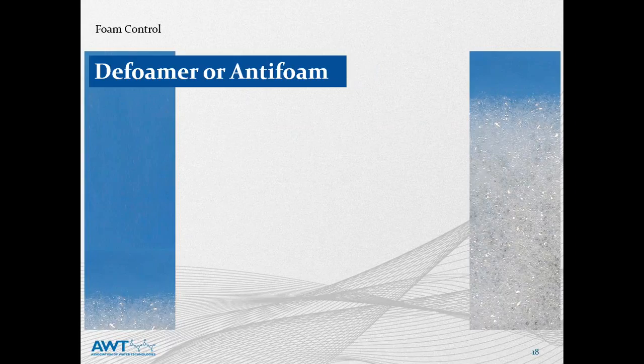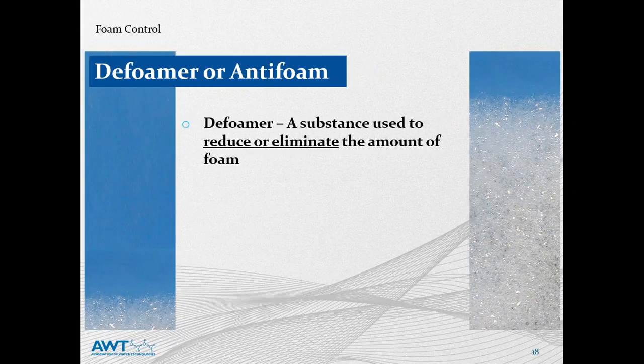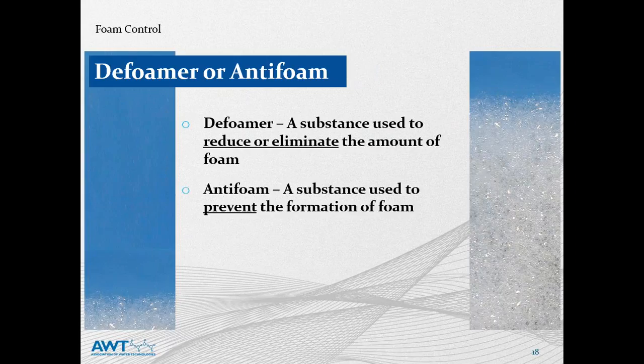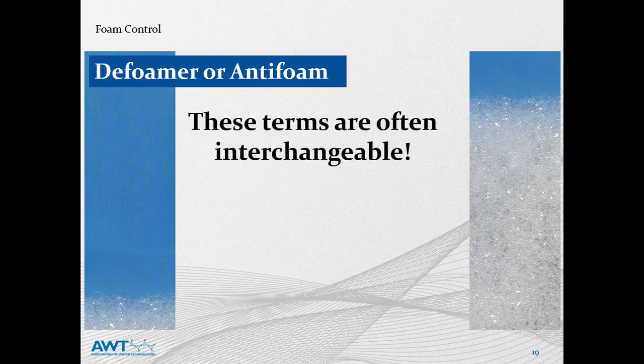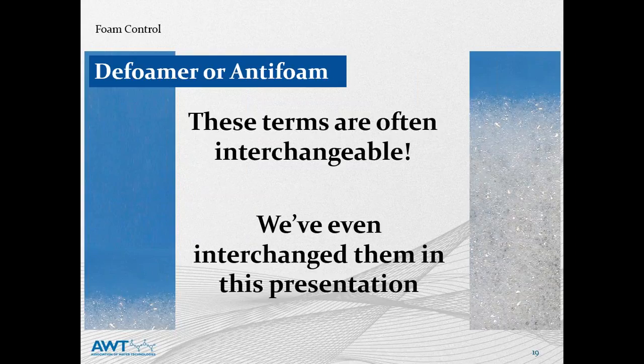It's really key to understand the difference between a defoamer and an antifoam. Simply put, a defoamer is a product that removes foam once it occurs — it kills, eliminates, or removes the foam. An antifoam is a product that prevents foam from occurring — you put it in and no foam will appear in your system. It's key to understand that for the most part, the chemistry of these products is exactly the same. It's just how the product is used and its functionality. Oftentimes these terms are very interchangeable, and you'll hear Katie and I refer to defoamer or antifoam back and forth, but it's about understanding the functionality of the product.